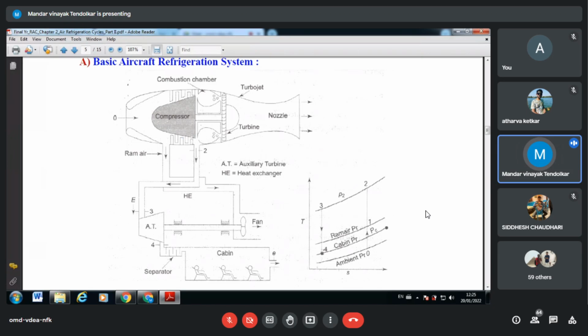We can call this an evaporator, though I'm not using that word deliberately, because as discussed in the last lecture there is no phase change here — evaporation is not the process. It's basically the sensible heat part, not the latent one. So I can say it resembles an evaporator, but in an actual evaporator it is always the latent part, while this is a sensible one. So let us call this the refrigeration load — in simple words, this is how the cycle completes.